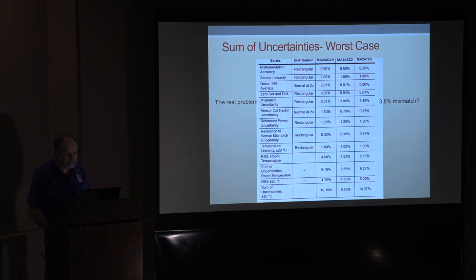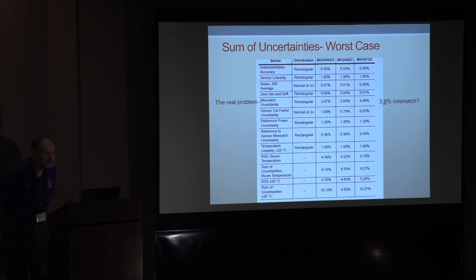Okay, this is a list of uncertainties from the Anritsu 2400 series power meter instruction book. If you look down the list, there are some that are not really big. The instrumentation accuracy is 0.5%. That's not too bad. You could probably improve that, but you're running up against sensor linearity, 1.8%. And linearity is not specified by any of the manufacturers of the power sensors. They'll tell you the correction factor, but they won't tell you the linearity. And at almost 2%, that really compromises a really accurate meter reading.